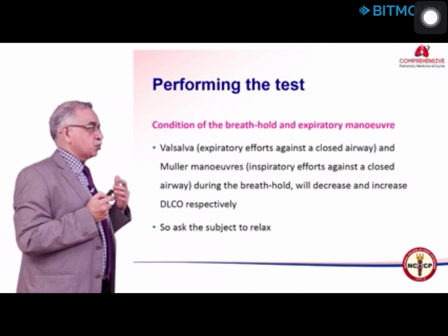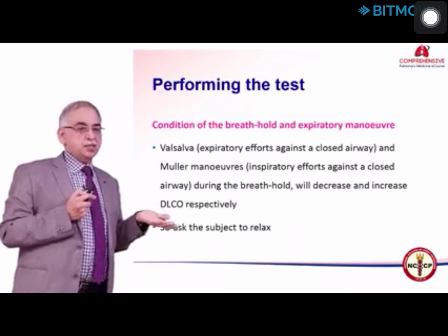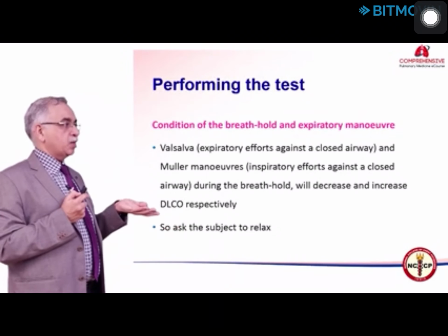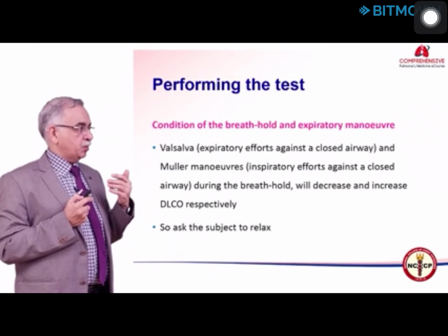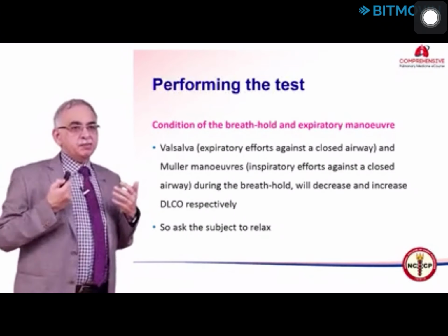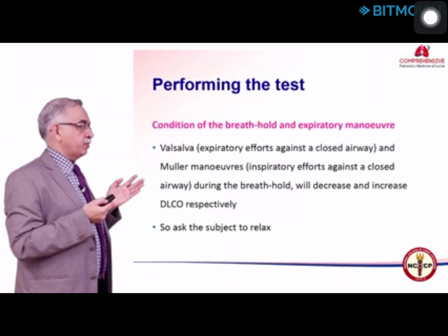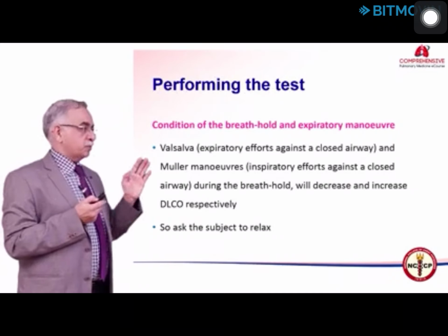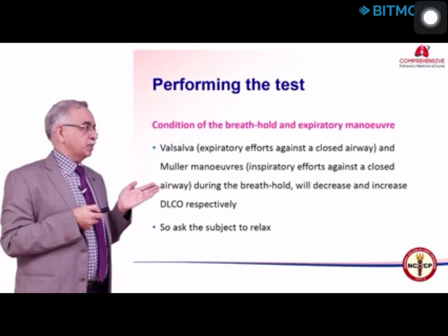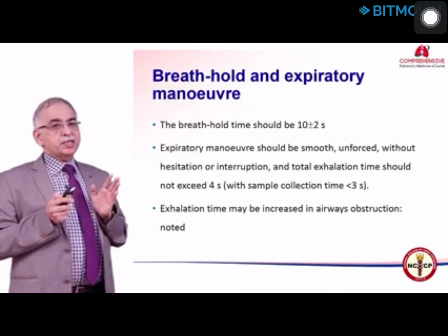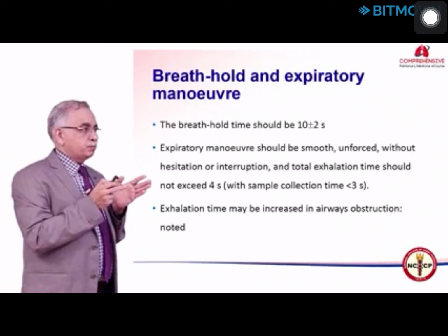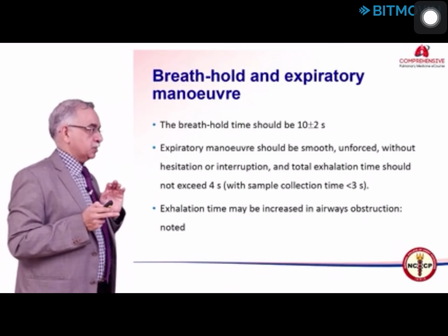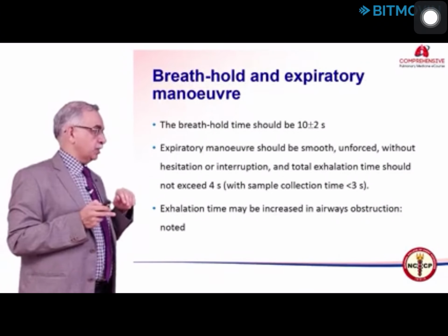If the patient tries to breathe against it, tries to exhale out or inhale in, that is a Valsalva or a Muller maneuver, that will change the blood volume in the thorax. So, that can affect the diffusion capacity. So, the subject must be asked to relax at breath holding. Breath holding time is set. Standardization is that it should be between 8 to 12 seconds, and this is software controlled.